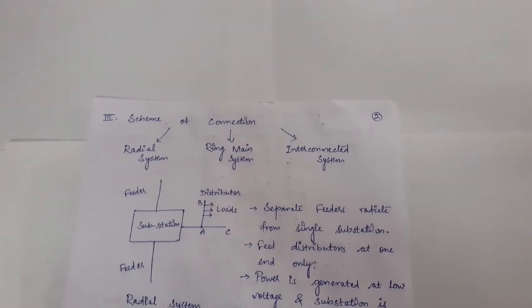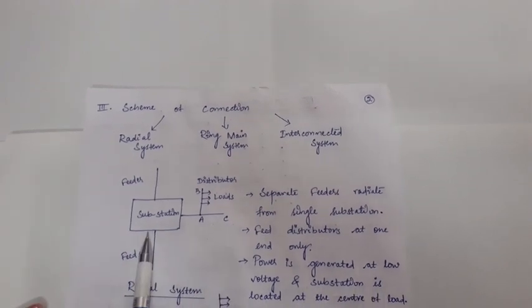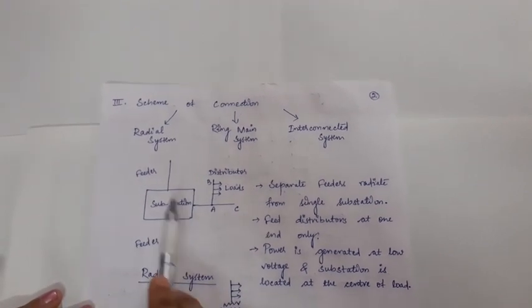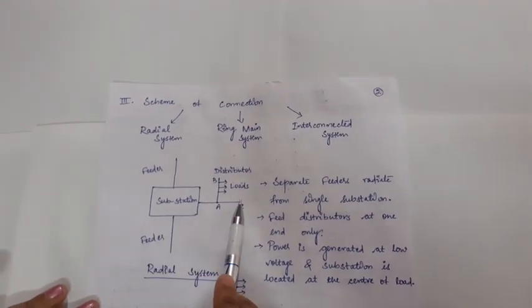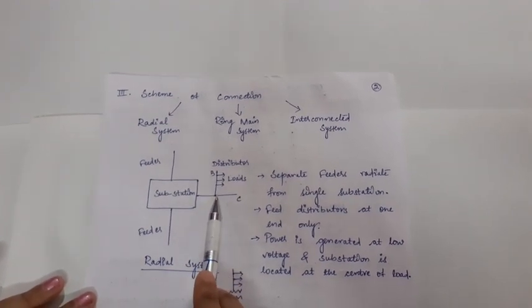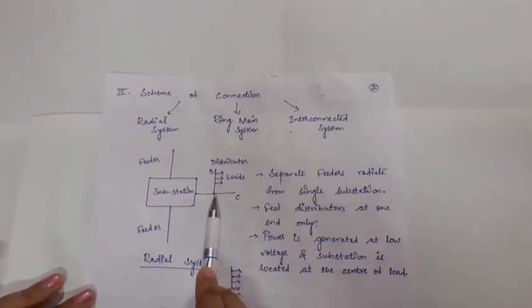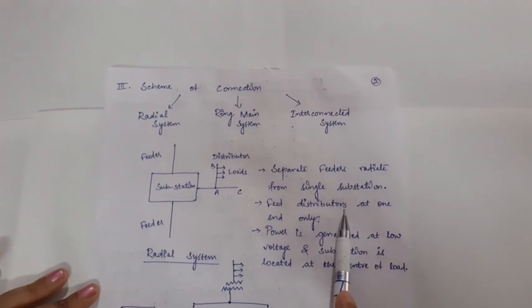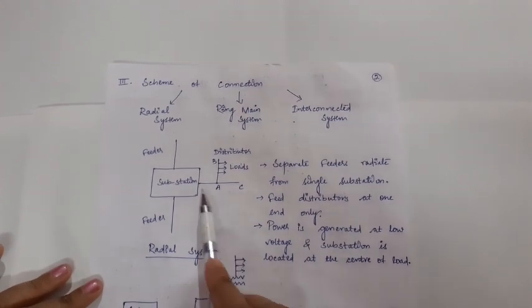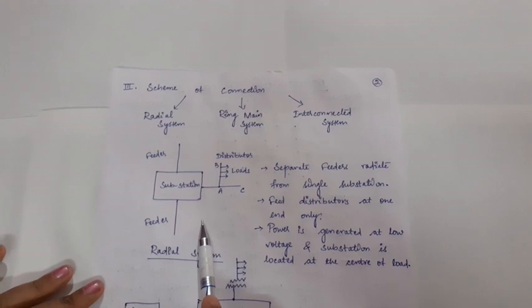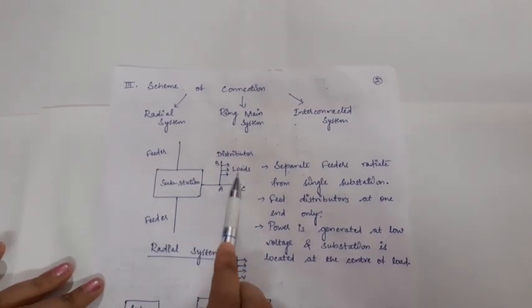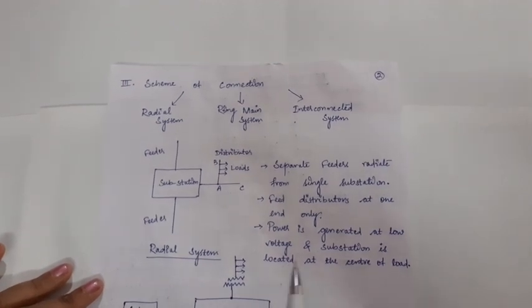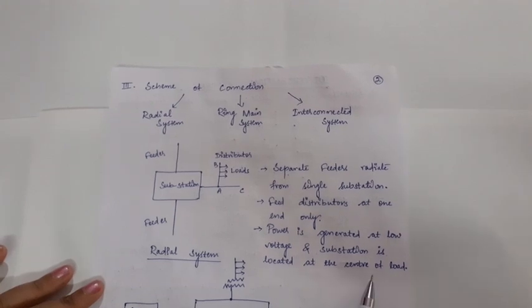In the radial system, the substation is the central part from where the feeders arise. From the feeders, the distributors are connected. Separate feeders radiate from the substation and feed the distributors at one end only, with one distributor per feeder. This radial system is normally used when power is generated at low voltage and the substation is located at the center of the load.